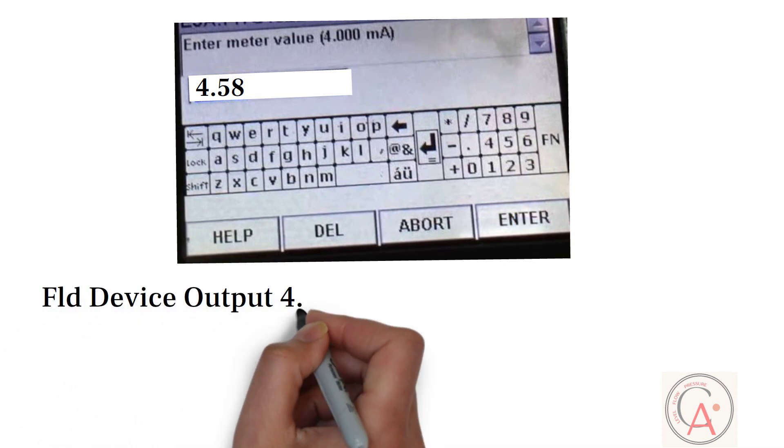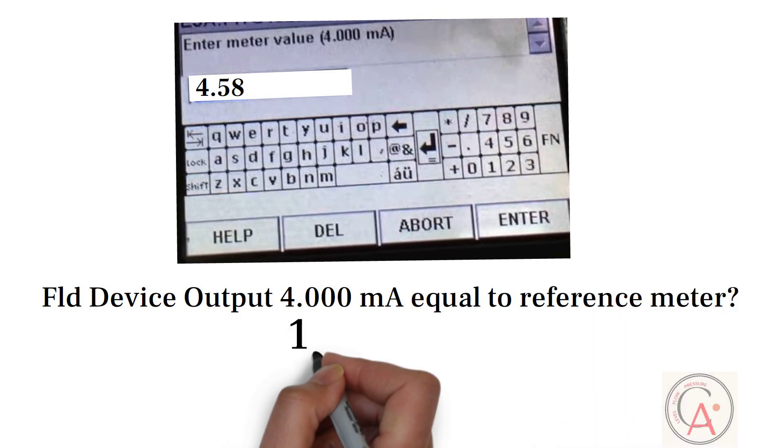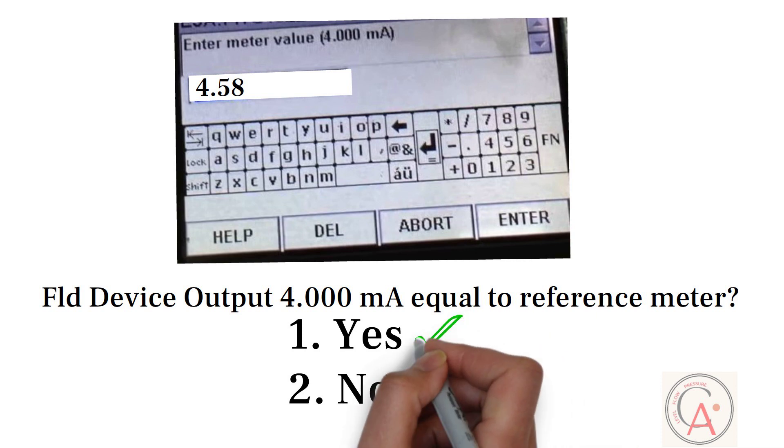Once you press ENTER button, field device 4 milliampere equal to reference meter message appears on the screen. And it has two options: yes and no. Select YES option and press ENTER button. Once ENTER button is pressed, analog output of differential pressure transmitter will be set to 4 milliampere.